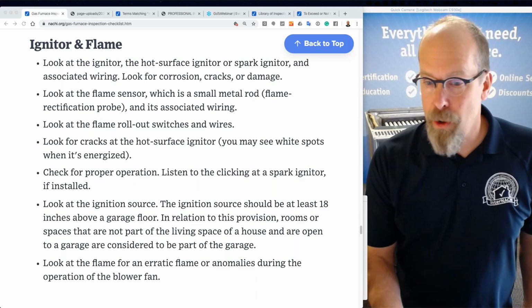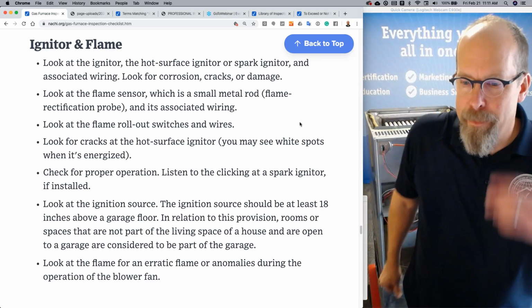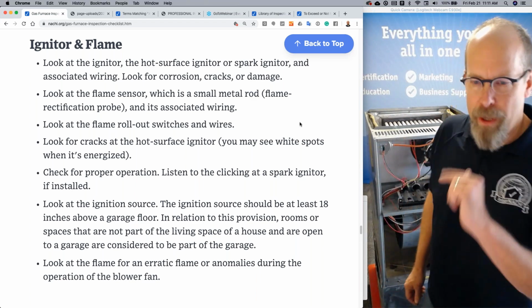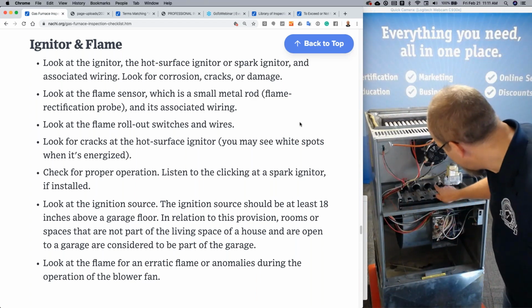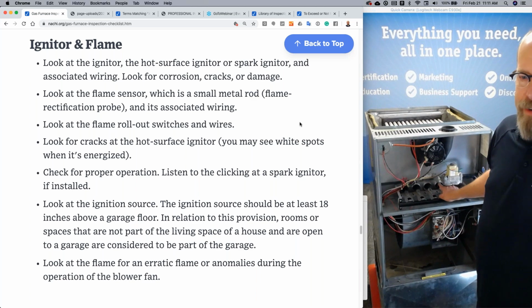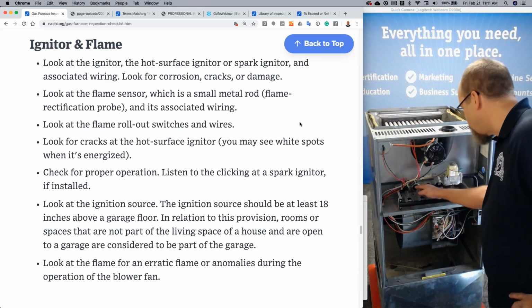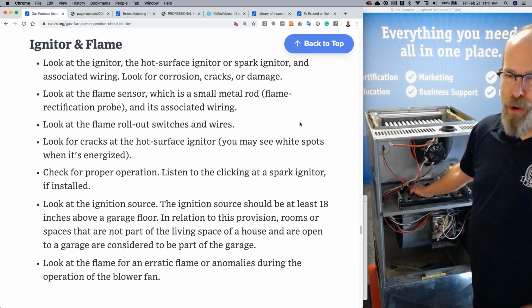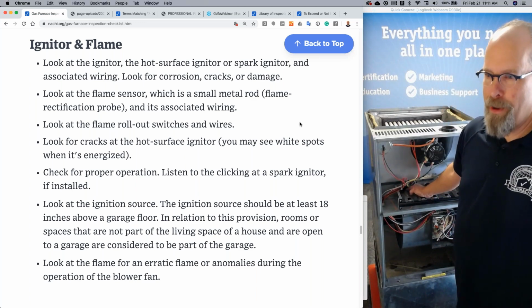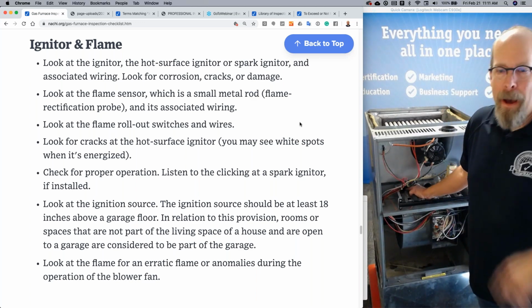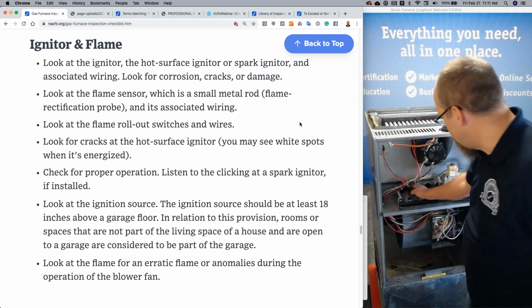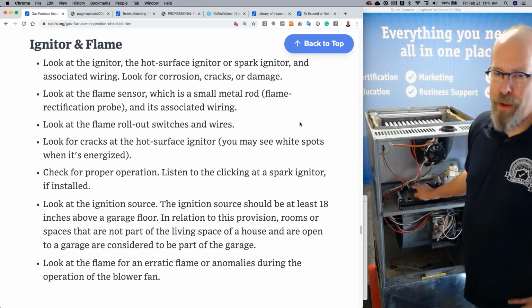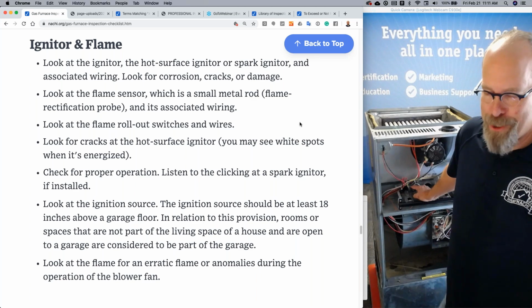Okay, so igniter and flame. Did we go? No, we didn't go over that. So look at the igniter. We saw that before. Hot surface igniter is what is here. The flame sensor, which is that small metal rod that we showed you, it's called the flame rectification probe. I wouldn't use that in my report. Look at the flame rollout switches, which is that thing just above the flame recognition or rectification probe.